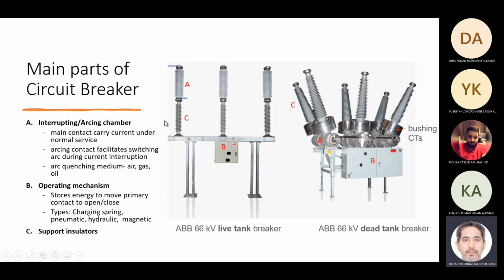So what are the breaker parts? These are the breaker parts, mainly 3 parts. The interrupting or the arcing chamber, which is, let's say, a high voltage 66 kV live breaker. This is the portion which is the interrupting, or they call it the arc chamber, in which the main contacts are located. The moving and fixed contacts are here. And these contacts are insulated either with air or gas or oil. And we have the operating mechanism, the mechanism that closes and opens the breaker.